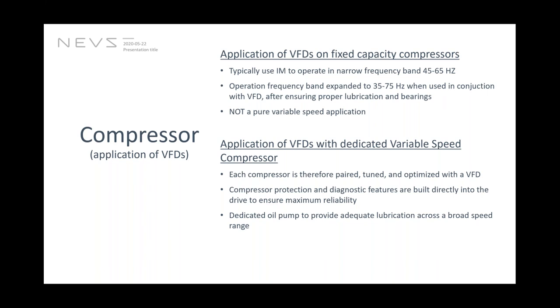When the variable frequency drive was developed, manufacturers started to look into whether they could expand the frequency band of the already existing compressors. But for that, they had to do quite a bit of testing to ensure that the lubrication and bearings work properly. And yes, they expanded the frequency band of those compressors from 45 to 65 Hertz to 35 to 75 Hertz. But anyway, these applications are not a pure variable speed application, but some products are still available with this sort of application.